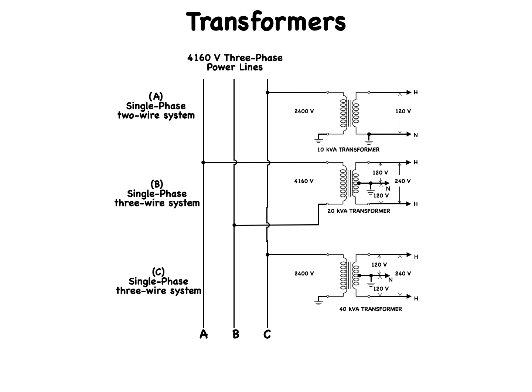The single-phase three-wire system has two hot lines and a neutral line. The hot lines, whose insulation is usually black and red, are connected to the outer terminals of the transformer secondary windings. The neutral line — the white insulated wire — is connected to the center tap of the distribution transformer. Thus, from neutral to either hot line, 120 volts may be obtained, used mainly for lighting and low power requirements. All of this information is given in this one concise three-phase schematic drawing.